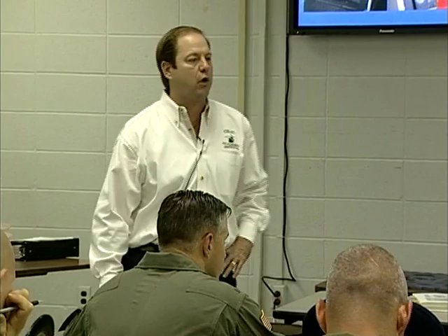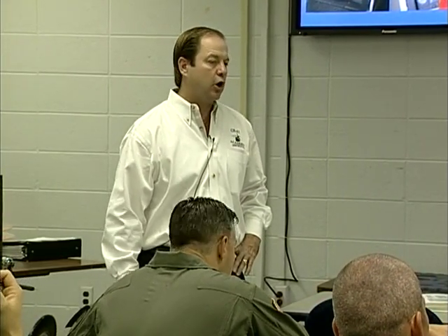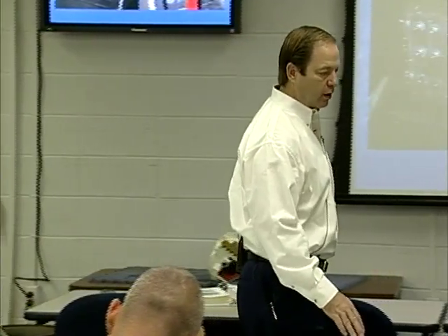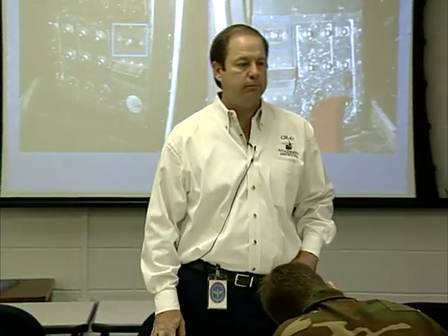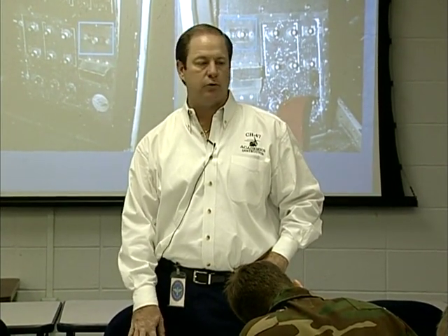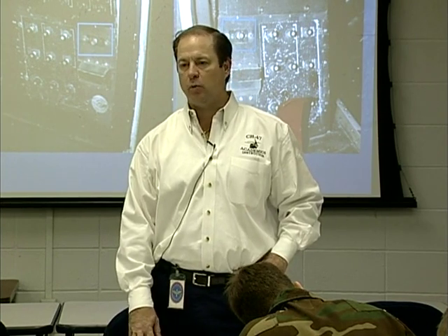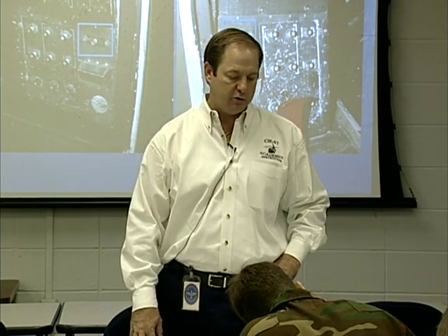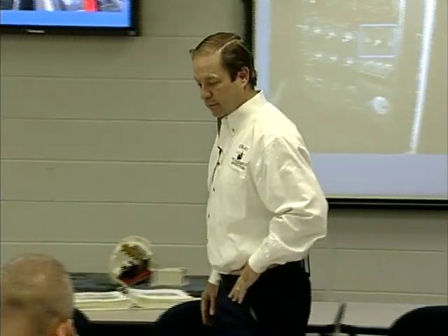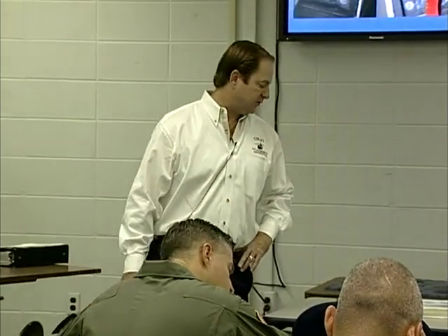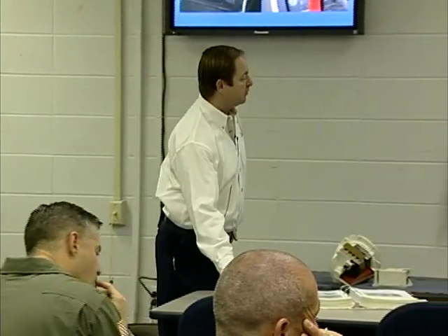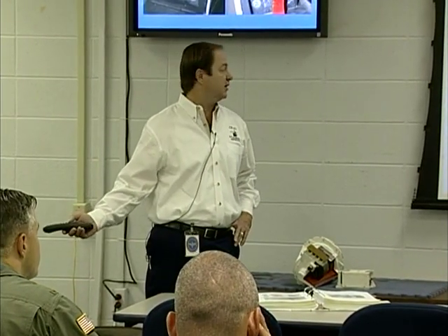Just like the AC system, located on your power distribution panel, we have what's called a cross tie. Again, a cross tie is just like its AC counterpart. It will allow for either one of those transformer rectifiers to power up the entire DC system. As long as that circuit breaker's in, it will automatically allow a single DC power source to power up the entire DC system.